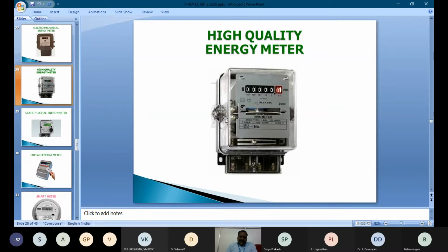It is very intact, and at the bottom of the disc we don't have any bearing at all. Normally a disc has a bottom bearing and a top bearing, but here there is no bottom bearing - the disc is under magnetic suspension, with a same-pole magnet provided at the bottom. Only the guiding bearing at the top is available, so there is no friction at all in this type of meter.